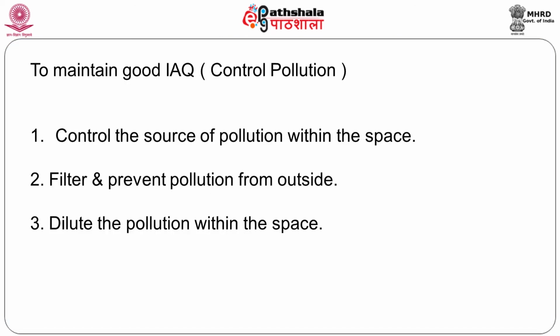Now, after both these, as I said, there are certain things which you cannot catch, you cannot minimize. So those things, you live with them and effect dilution by putting in more fresh air. So you could, for instance, say, look, my janitorial practice is in the morning at 9 o'clock. At 9 o'clock, I have humidity added on. So technically, a good air conditioning man can say, at the time my floors are being mopped, let me increase the fresh air by 10%. Let me increase my fresh air by 20%. It will mean a marginal increase in heat load, but a phenomenal improvement in air quality.